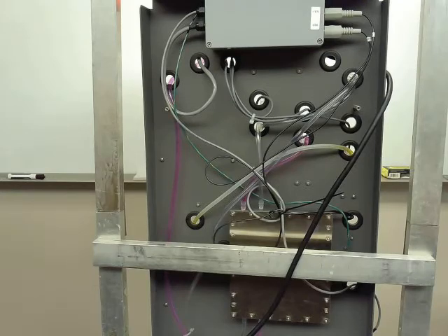Again, just because we're basically etching off the top layer of glass, if you do it too many times, there won't be much glass left. I can't say that if you do it 10 times you're going to be out of glass, but each time you do that, you slowly decrease the life of the sensor. But most of the time with the regen, you probably won't even have to do it for at least a few months, maybe a year.